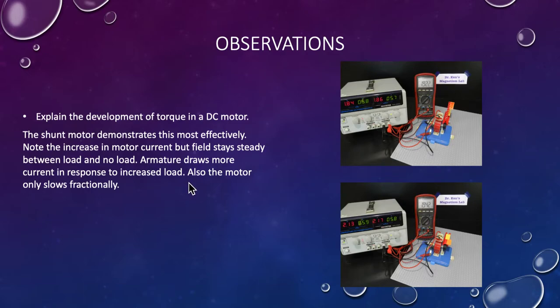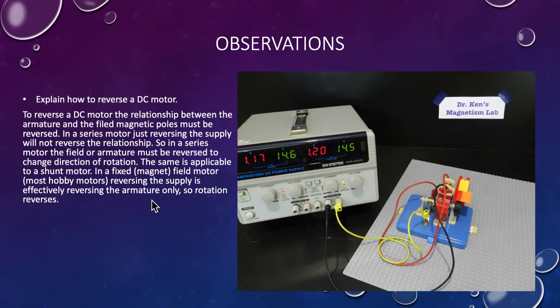Development of the torque of the motor. The shunt motor demonstrates that this is most effective. Note the increase in the motor current, but the field stays steady between load and no load. The armature draws more current in response to an increased load. Also, the motor only slows fractionally.